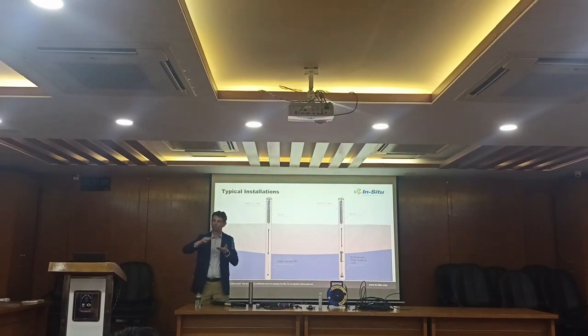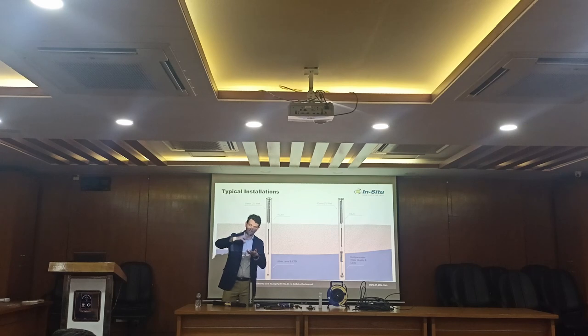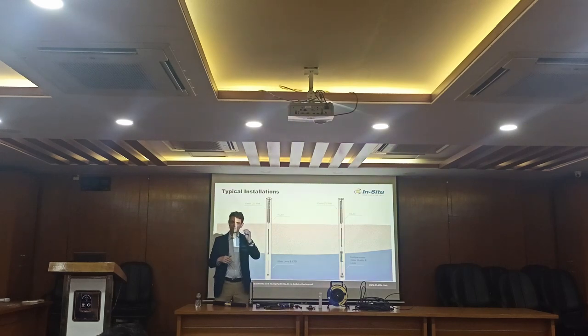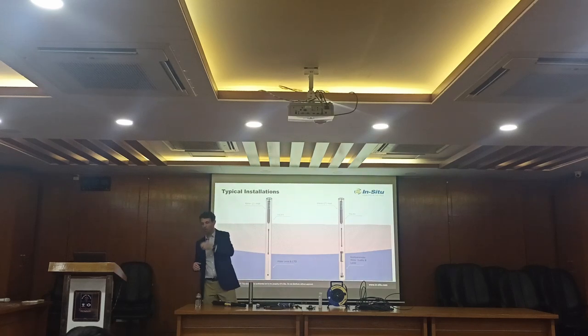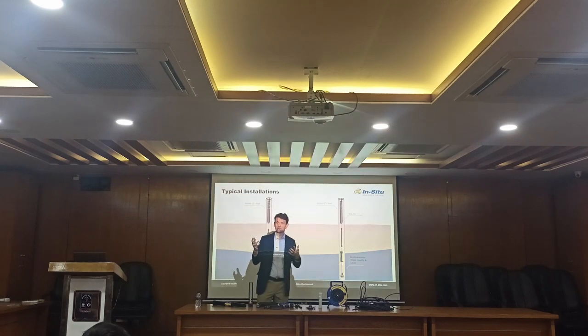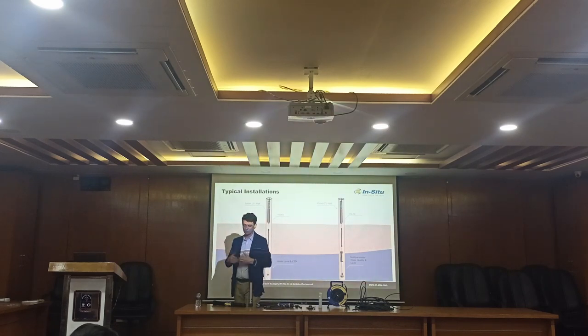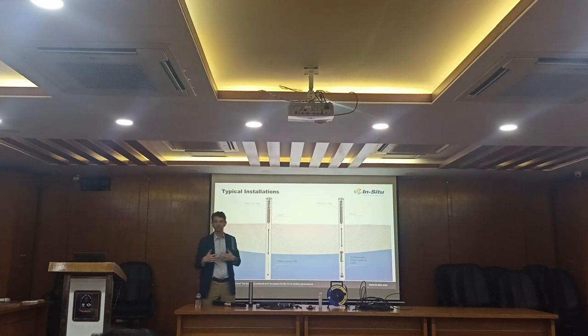You have to be able to refill that. In addition, depending on the type of water you're dealing with and the electrolyte level in there, the calibration will change. So with older instrumentation, many people calibrate again as needed, depending on how they're using it. But with long-term deployment, they were finding they're only getting maybe a week, maybe a month at most on their calibration.